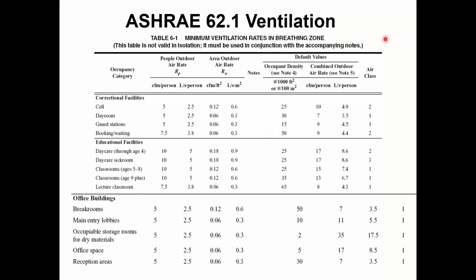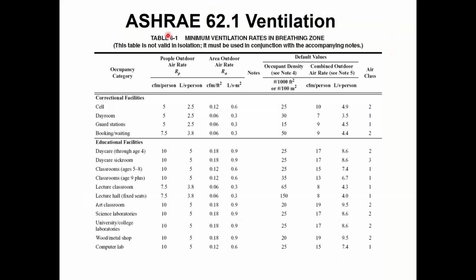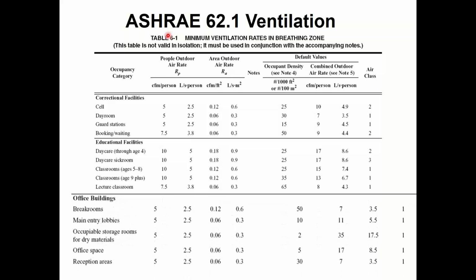So for you guys that joined us last week, just know the short version is for every state and or municipality, there's a mechanical code, and it's probably based on ASHRAE 62.1 or the International Mechanical Code. In either case, it would have tables like this, probably 4 or 5 pages worth. In my example last week, I used an office building, which required 5 CFM per person plus 0.06 CFM per square foot. And those two numbers get added together, and they only apply during occupied hours. During unoccupied hours, you can go down to 0. And in fact, for the energy code, you have to go down to 0.